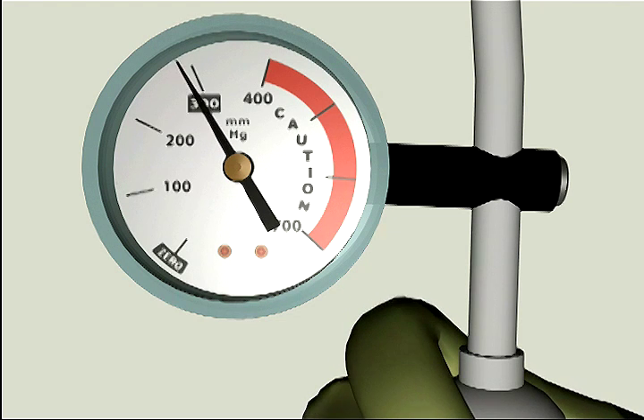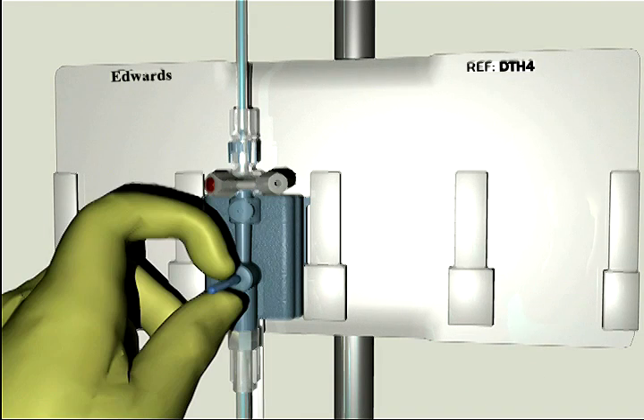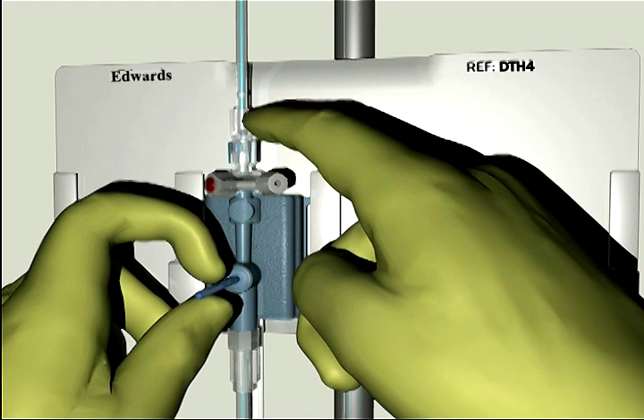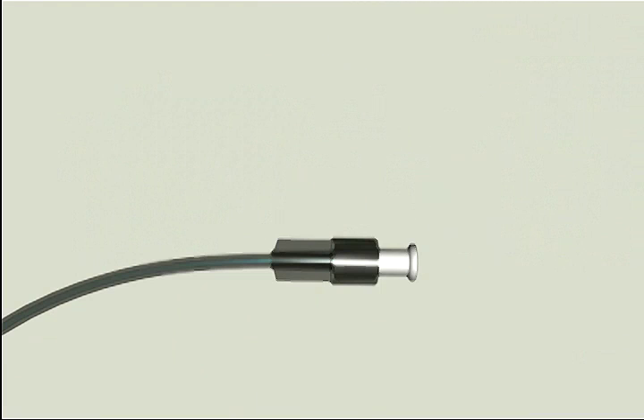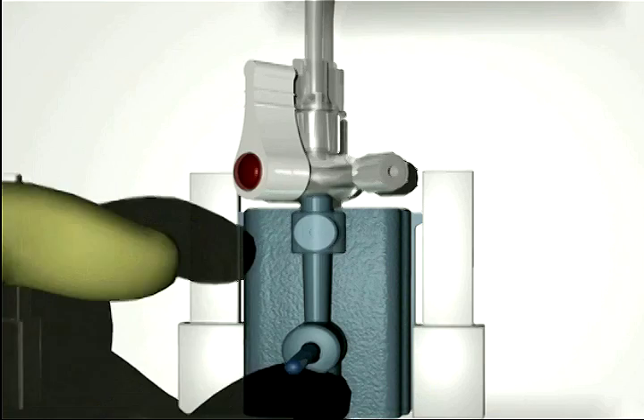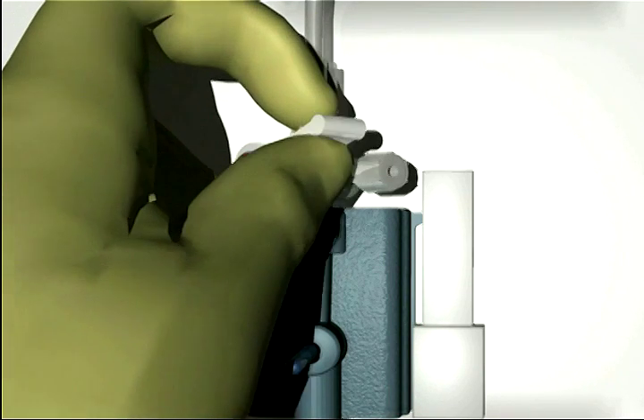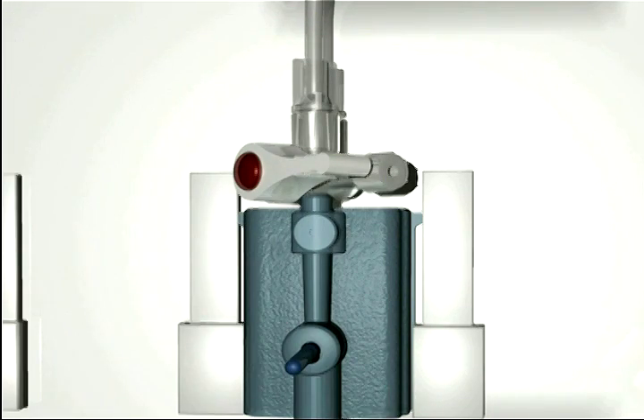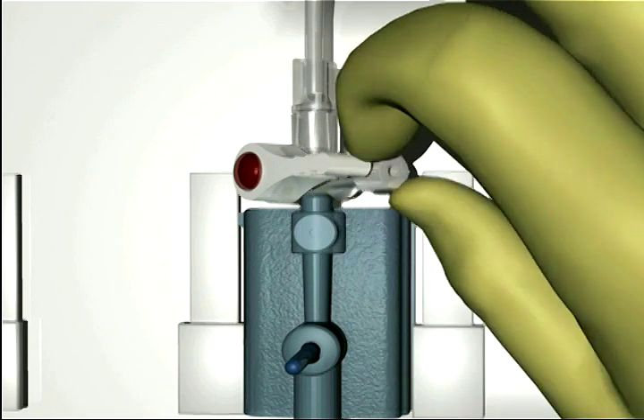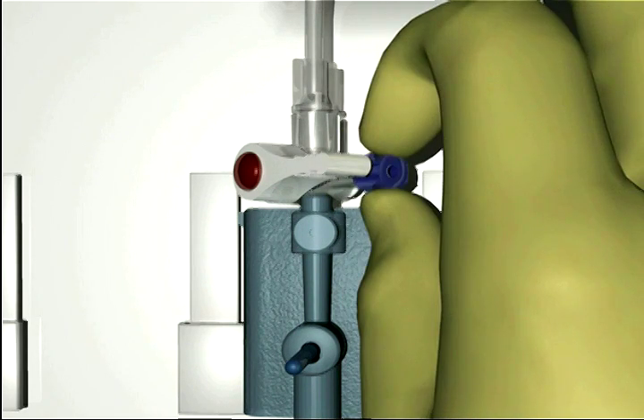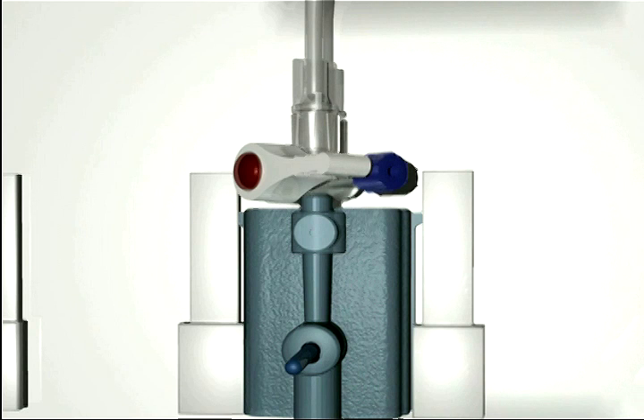Pull the snap tab to flush the system under pressure while tapping on the tubing and stopcocks to remove any residual bubbles. After removal of any residual bubbles, connect the TruWave transducer to the bedside physiologic monitor for calibration. Step 6. Replace all the opaque vented caps on the side ports of the system stopcocks with non-vented caps. Now that we have completed priming the system, we will need to calibrate the TruWave transducer with the bedside physiologic monitor. Use the following 8 steps.